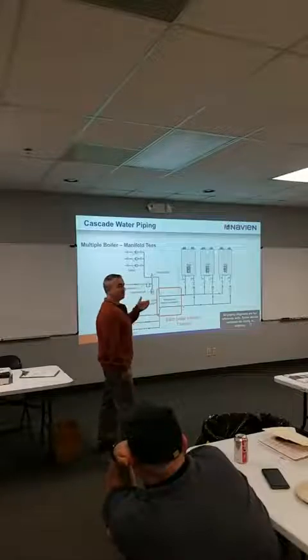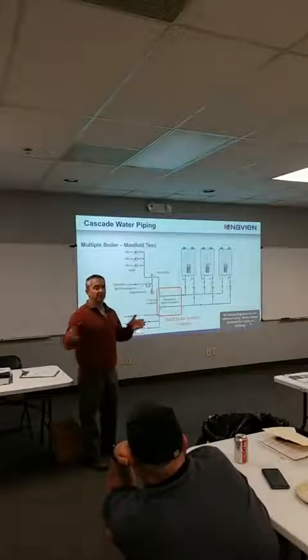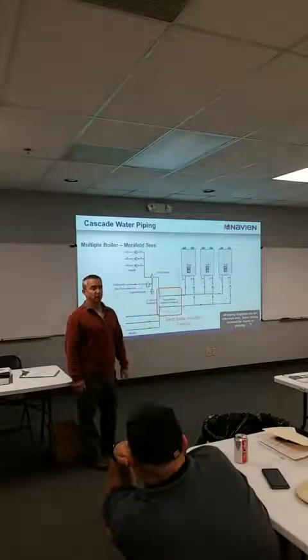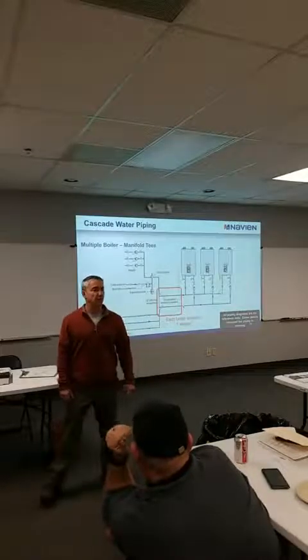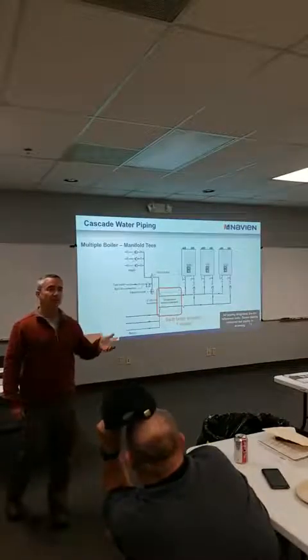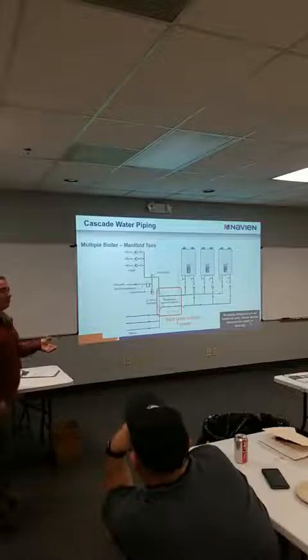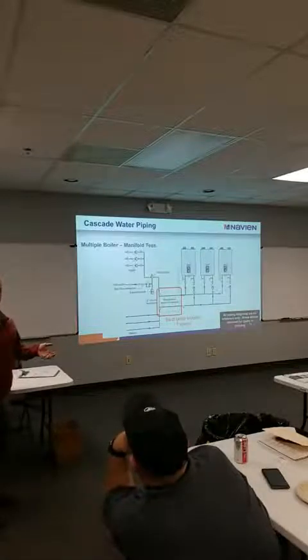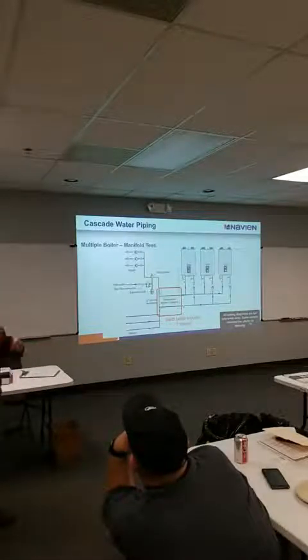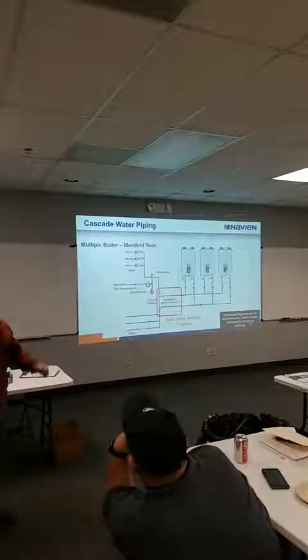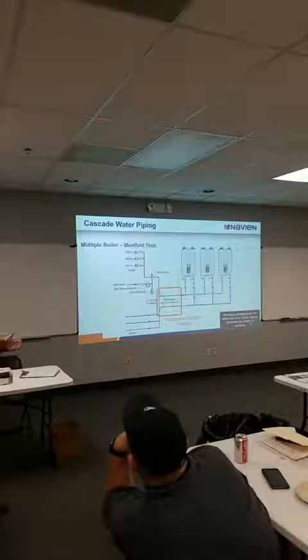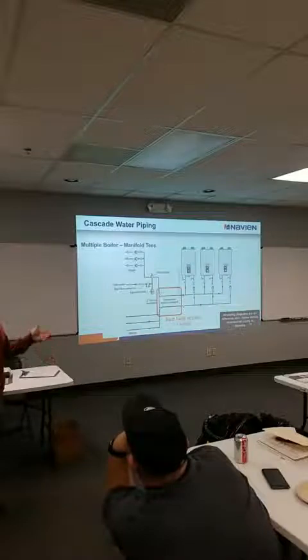When we have a bank, we always fire half the bank and then just figure out where to go from there, depending on if we're managing temperature or not. And then they'll ramp up and down, turn themselves on and off at about an 80 percentile. Oh, in parallel though? Yep, and then they equalize runtime. So the main unit, that's just to do setup. After that, it doesn't really matter. It's a random sequence of events that are turning things on and off and to equalize runtime across the bank.